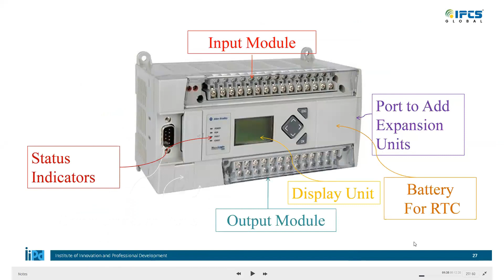PLCs are normally categorized based on their inputs and outputs. There are discrete inputs like sensors, switches, limit switches, push buttons, pressure switches, temperature switches, and flow switches — on-off sensors — as well as analog sensors like temperature transmitters, pressure transmitters, flow transmitters, radar transmitters, rotational sensors, and G-force sensors. So discrete means on and off, while analog means continuous — for example, controlling fan speed from 0 to 100%, not in steps but continuously from 0, 1, 2, 3 up to 100.